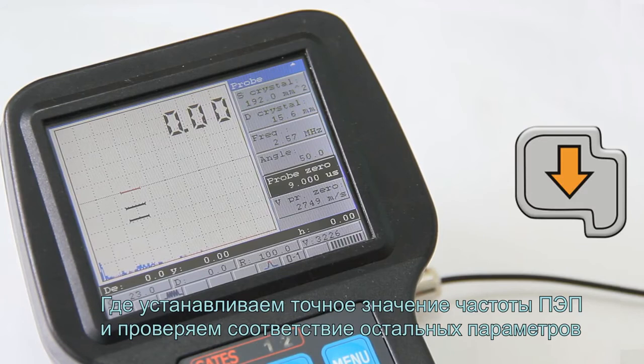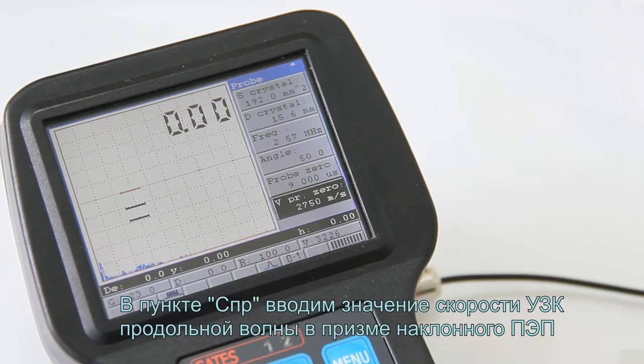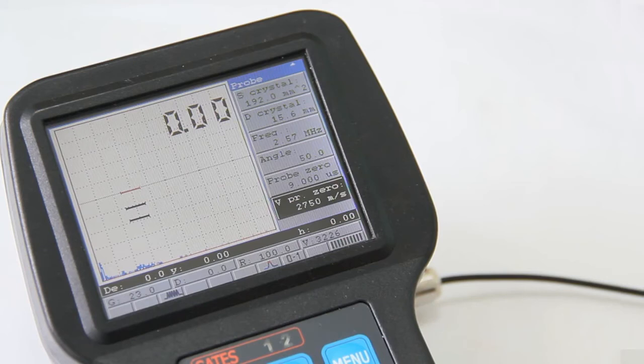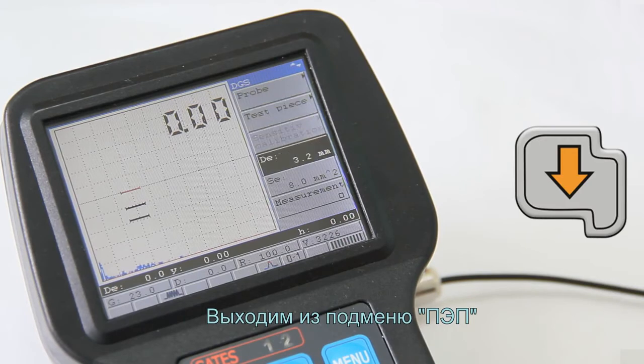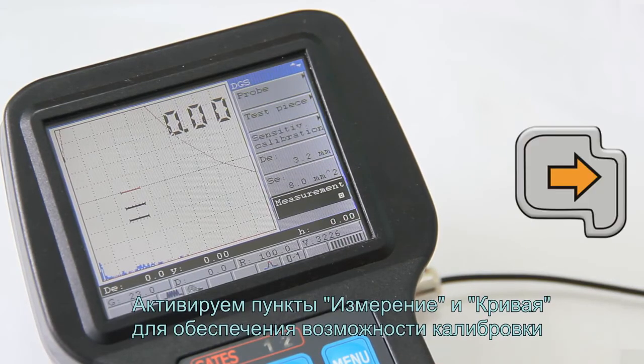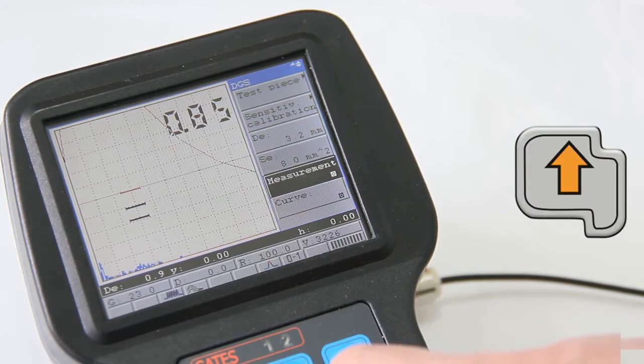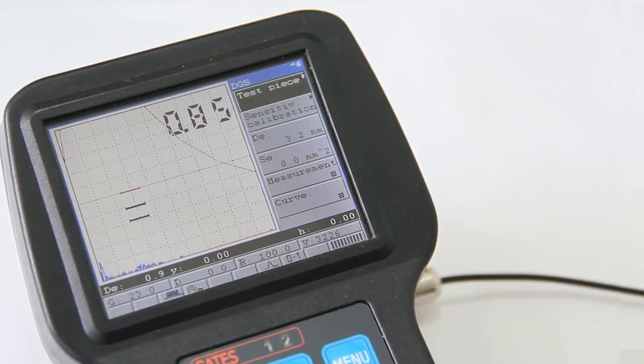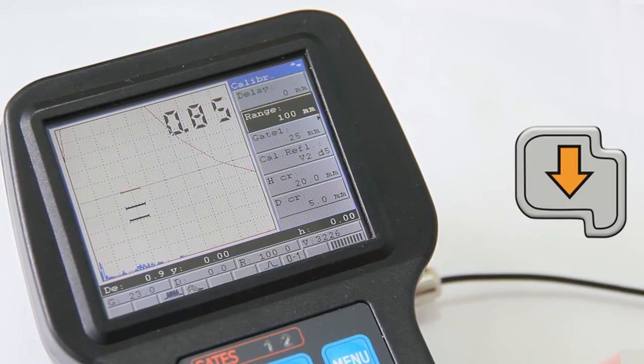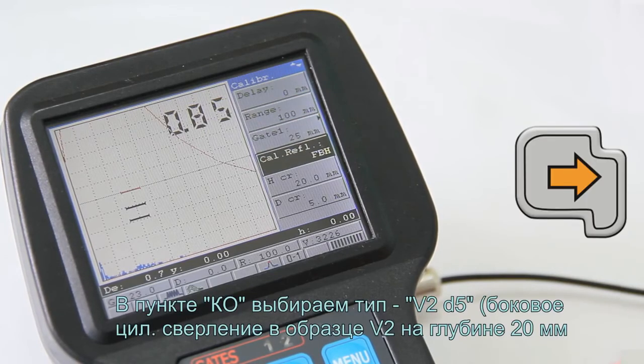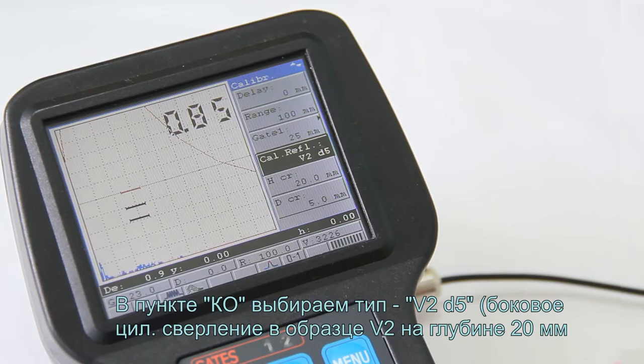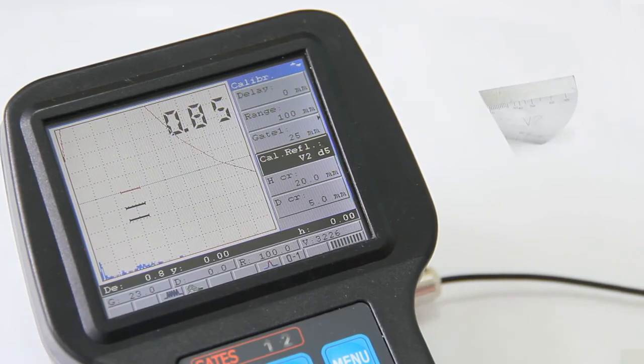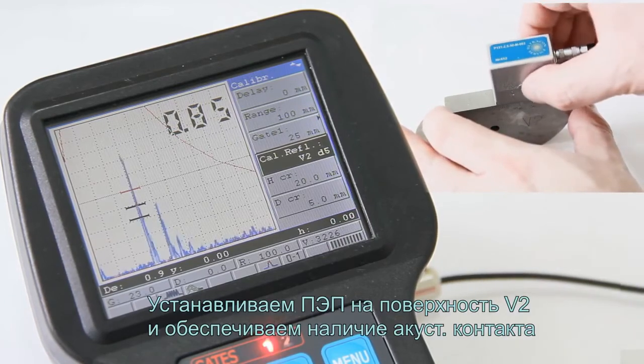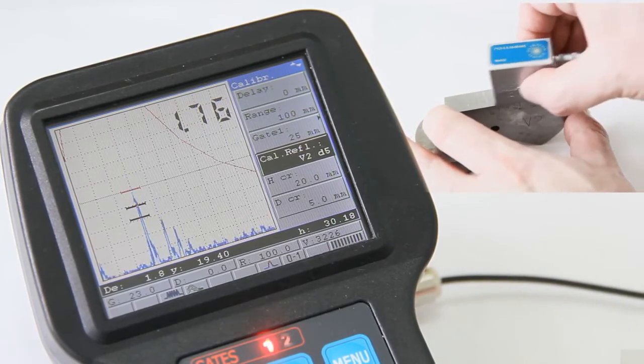In V pr zero item, probe zero velocity, enter the value of longitudinal velocity in the angle beam probe wedge. Exit the probe submenu. Activate the item's measurement and curve to ensure the possibility of calibration. Enter the submenu Sensitivity Calibration. In Calibration Reflector item, select the type of V2 D5 side drilled hole in V2 block at a depth of 20 mm. Place the probe at V2 block surface and ensure the presence of acoustic coupling.